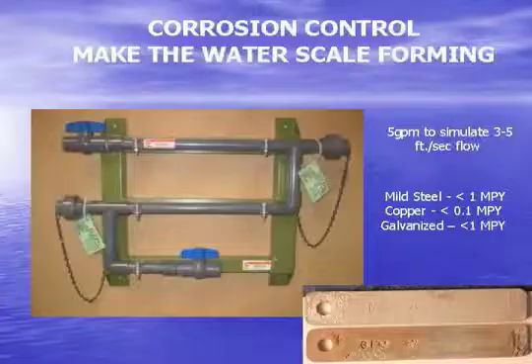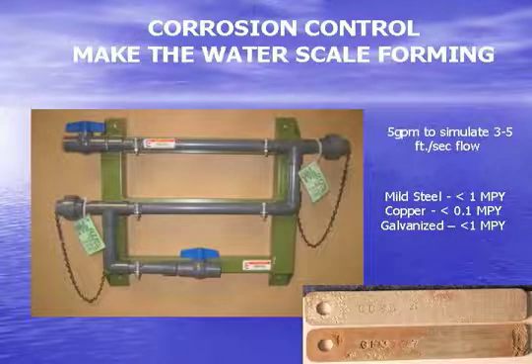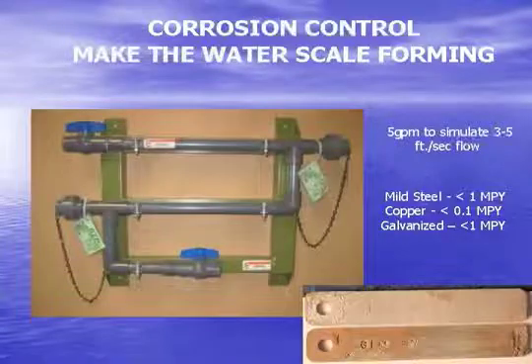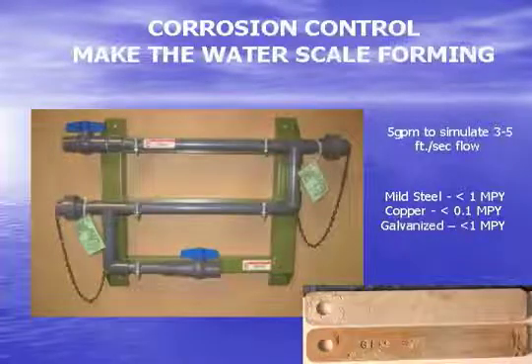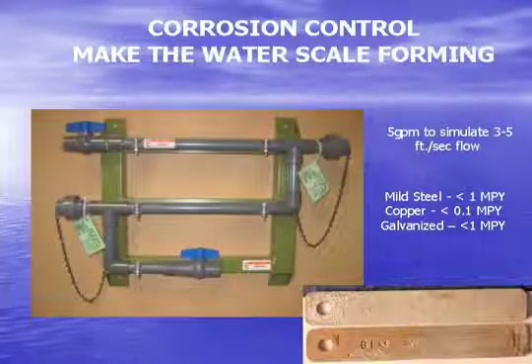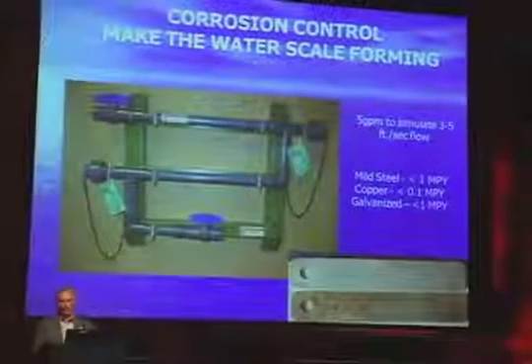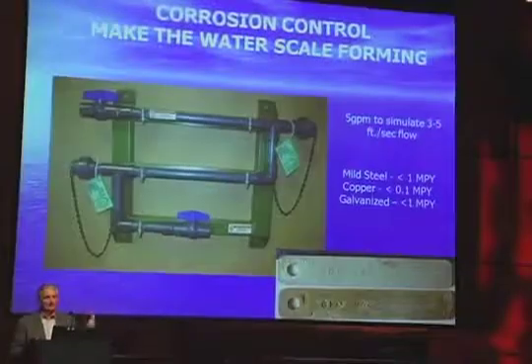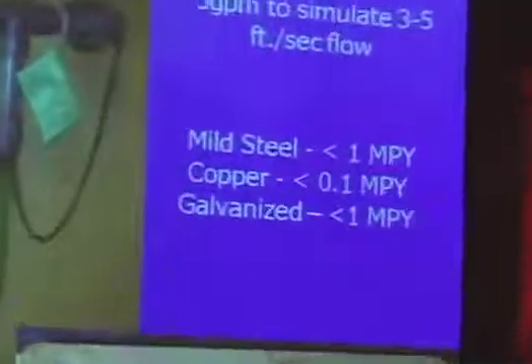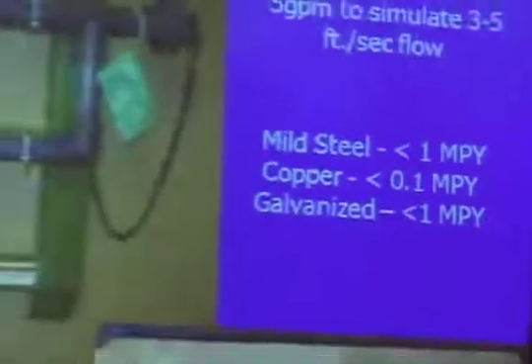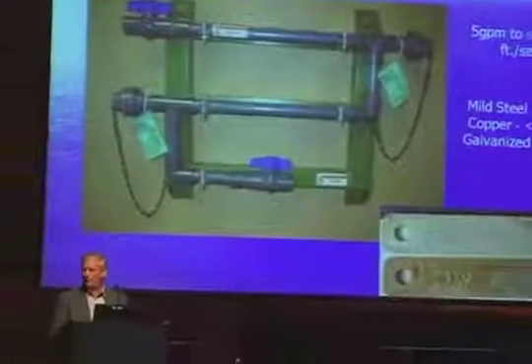One of the things you want to do to make sure things are going well is put in a corrosion coupon rack. These are racks where we have small pieces of metal strips pre-weighed to the fourth decimal point — a known surface area and known weight. We put them inside the corrosion coupon racks and simulate three to five feet per second flow, which is what you're seeing through the system normally. We set that through a water meter where we control five gallons per minute. Normally a five-gallon-per-minute, one-inch rack will simulate three to five feet per second. The goal is to pull those coupons out about every 90 days, have them cleaned and re-weighed — that tells you your mils per year thickness. It gives you four or five indications per year before you open up that chiller, so you're not surprised. Mild steel should be less than one mil per year, copper less than 0.1, and galvanized less than one mil per year. If you're exceeding those limits, that gives you an opportunity to make adjustments before you get a surprise when you open the chiller.